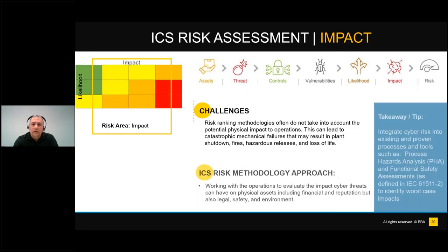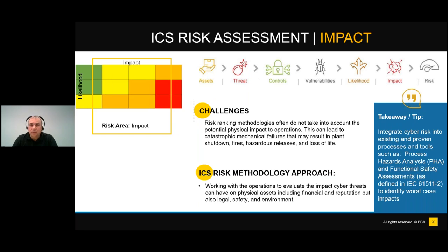For impact: if your organization is already doing process hazards analysis and has data available on impact, it might make sense to use that data. Key impacts to include are interruption of service, plant shutdowns, environmental impacts, or loss of life. Risk evaluation looks at different scenarios through two common approaches: qualitative and quantitative analysis. Quantitative risk analysis is less common due to the lack of data in OT/ICS cybersecurity. Qualitative risk analysis is a simpler evaluation used to quickly identify and manage risks before they exceed a threshold. Quantitative analysis is a more exhaustive examination using numeric values.